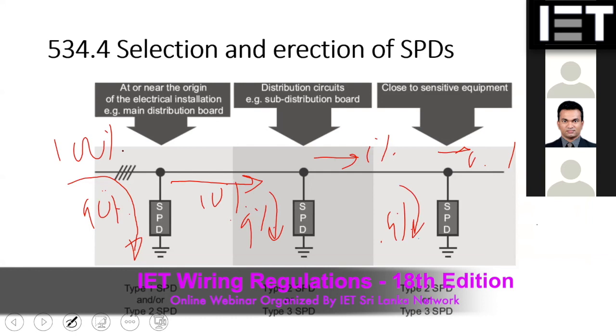The reason the standard highlights this is that we are using more and more power electronic based equipment. Something like 10 to 15 years back, we were using incandescent lamps. Now we never use incandescent, they have all been replaced by LED. Even fans and other equipment now come with electronic drivers and electronic components, which are very vulnerable to over voltage situations. So this has now become a mandatory requirement, not like earlier installations. In new designs, you have to evaluate the risk, and then you have to incorporate transient over voltage protection into the building design.